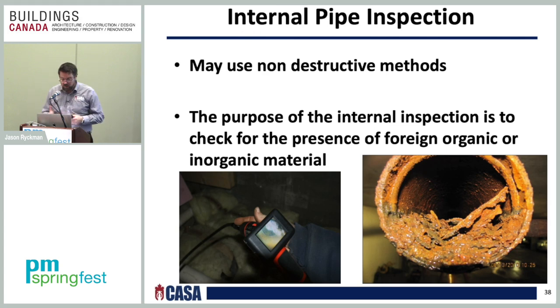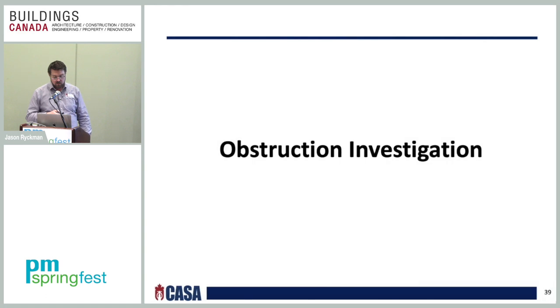Also, to do your internal inspection, you can use non-destructive methods. You can use different types of scans and so on to go through the pipe and do your inspection that way. So the standard does allow you to use other means to inspect that piping to make sure it's not obstructed. So that's the internal inspection requirement in Chapter 14.